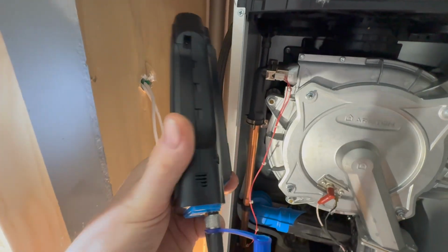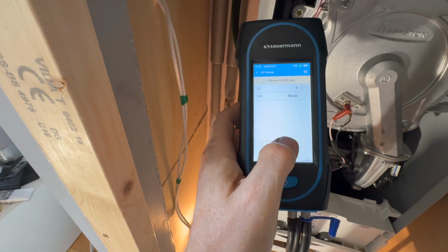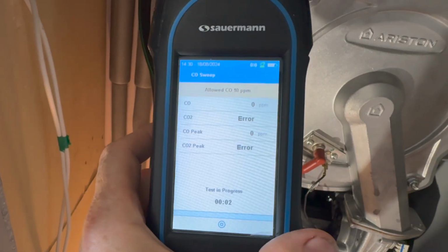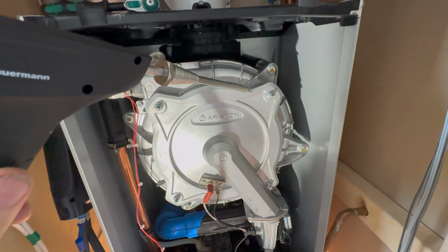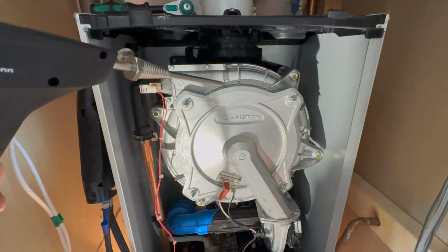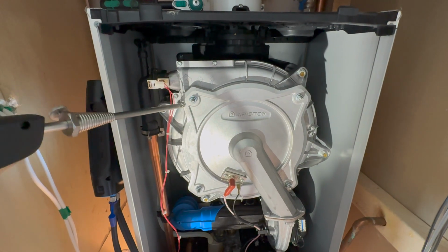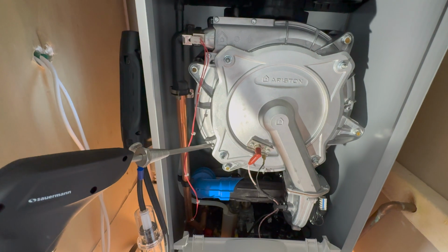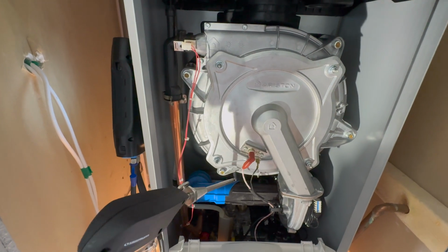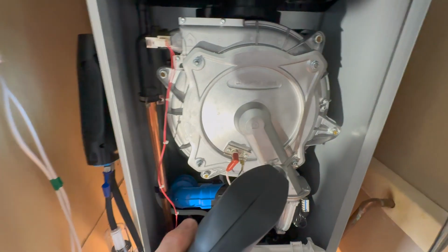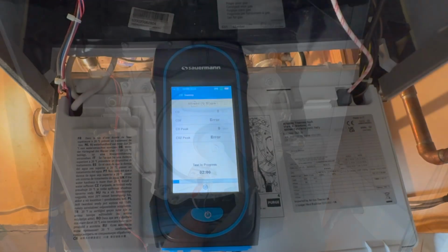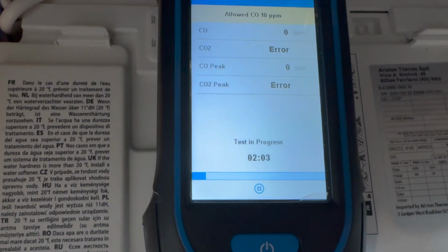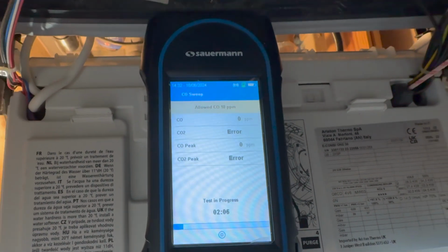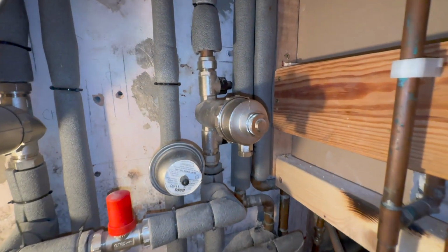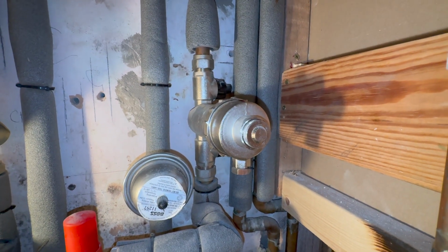Then I can take my Sauermann analyzer and start the test. And I can now use my probe to go around the heat exchanger for 2 minutes and see if I actually get any CO coming out of this gasket. So 2 minutes are up and the reading's 0. So that's good.